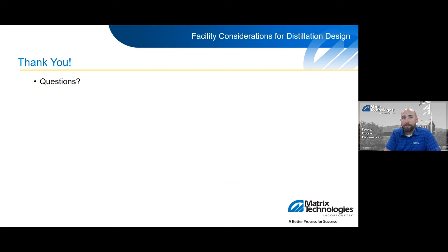And there's another question, somewhat related to this topic: can you touch on the topic of ventilation being used to reduce the electrical hazard classification? I guess the question is, is that possible? Yes, I have seen it, and we have used that in the past. As long as you meet the requirements of the air changes per hour, I have seen that drive your classifications down. It will shrink your bubbles a little bit. Again, I referenced back to the code on that, and then your insurance company. Even your fire suppression systems can help dictate or drive down some of the classifications. But with that ventilation, you need to have that backup power source to ensure that you can maintain the classification level no matter what happens.